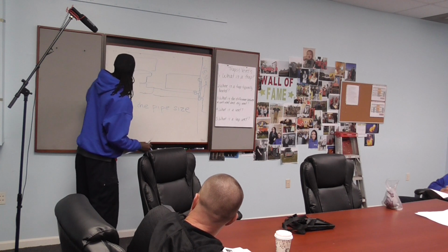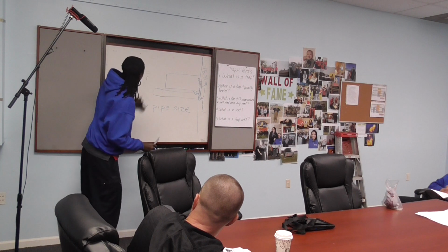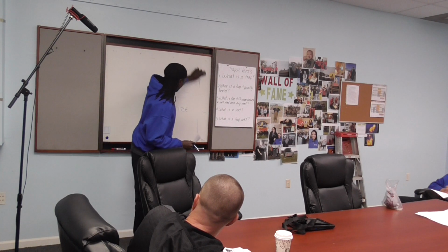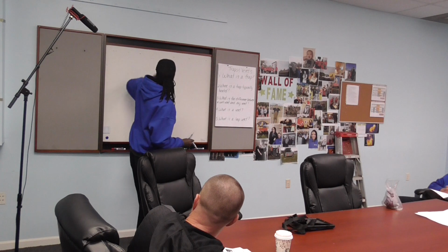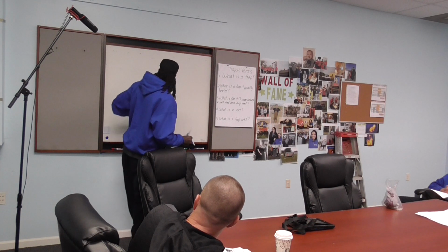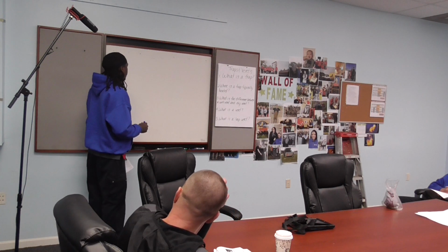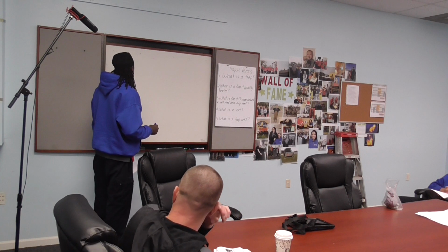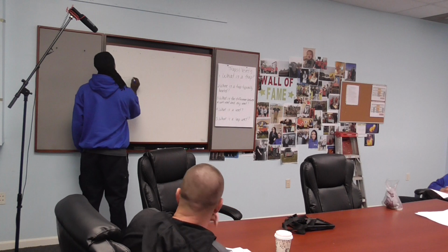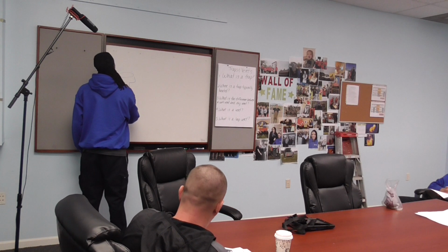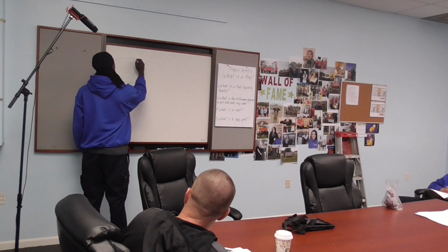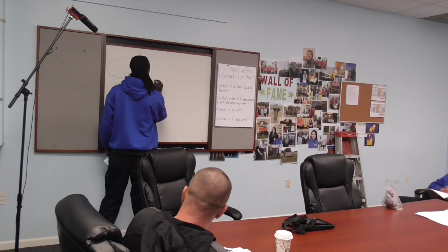A lot of problems that a lot of people are having is that certain fixtures aren't being vented. They're being shared. I went to this one lady's house where you flush your toilet, and her tub starts gurgling.